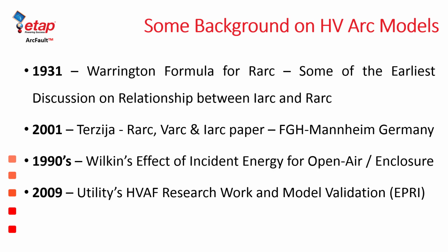Decades later, the works of German researchers such as Stokes and Oppenlander of the FGH Mannheim laboratories provided the foundation to what we call in ETAP ArcFault Method 1. Method 1 in ArcFault, as you will see in future slides through this presentation, is called the Stokes-Oppenlander arc flash method, and is suited in particular to the IEC standard application.